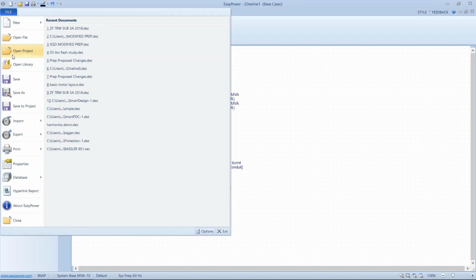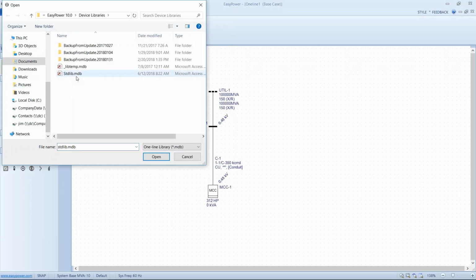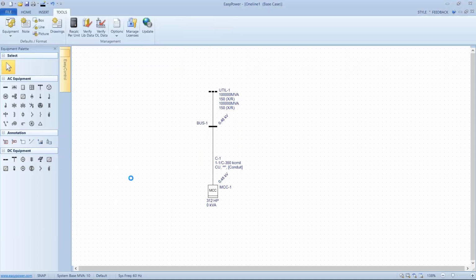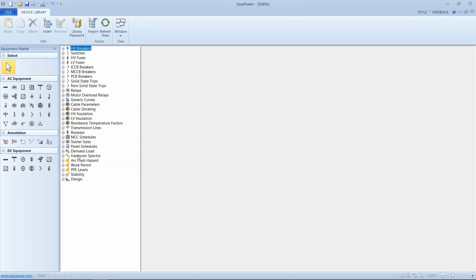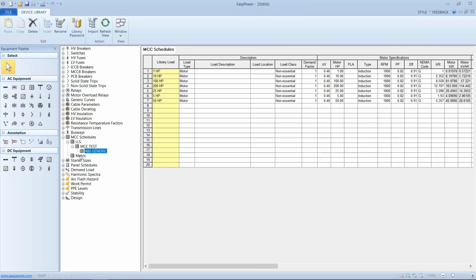The way I did the library load is I come back to my library, and this can be done for panels as well, and that is create a series of loads that are pre-configured. What I'm looking at are motor control schedules. Here's my MCC test. Here's my 480 volt generic. So the way I envision, at least what I was planning, let's say I use Square D frequently for my protective devices. I might have a 480 volt Square D library load. I might also do a second one or a third one for a Cutler-Hammer and another one for Siemens.